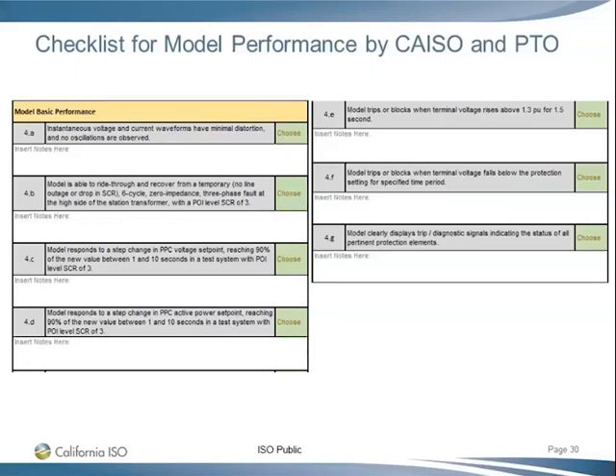Okay, perfect. So that's one. Then the other one, I've seen it in the EMT modeling requirements by California ISO. One of the items is including the transformer magnetization curve. Does that mean that we need to include the transformer magnetization curve that comes from the OEM, or do we need to model it, let's say, with the basic model in, for example, PSCAD and use the match function and include that as a report or as an appendix in the report? Do you just want to know that the transformer magnetization has been modeled properly in PSCAD, or are you just after the curve from the OEM? Yeah, we want you to include that magnetizing curve in the PSCAD transformer model. So there's a place you specify the curve. Just include it in there. You model it correctly. That's all. Okay, perfect. Thank you.